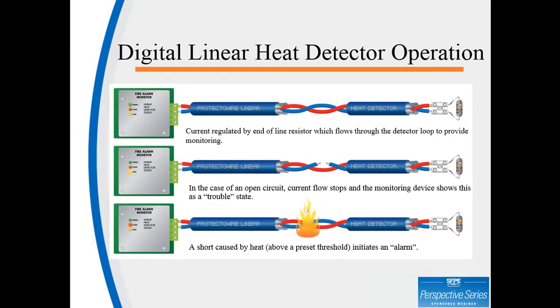Now we'll talk about digital linear heat detector operation. What you see on the screen is three graphics showing the different states of operation of the detector itself. In the first graphic, we're showing a closed loop circuit which is monitored by the end of line resistor. So the current flow going through the resistor shows the control panel or monitoring device that the circuit is intact. The second graphic shows a break. In the case of an open circuit, current flow stops and the monitoring device shows this as a trouble state or condition. The last graphic shows a short caused by heat above a preset threshold, which indicates an alarm. As we mentioned before, when in a heated condition, the polymers melt, the two wires touch, and the short is seen by the monitoring device as an alarm condition.